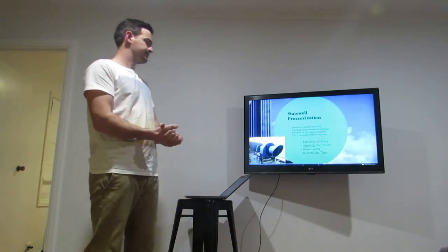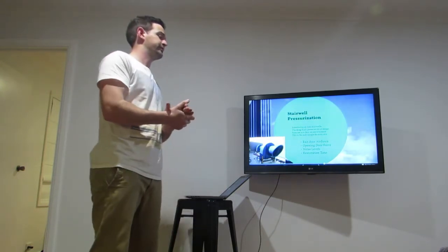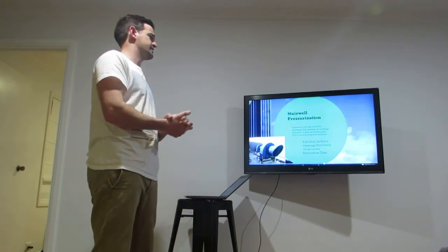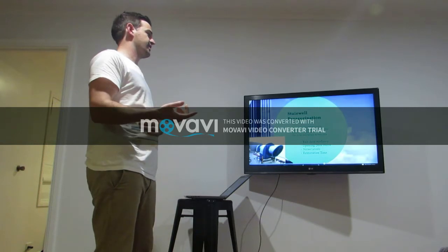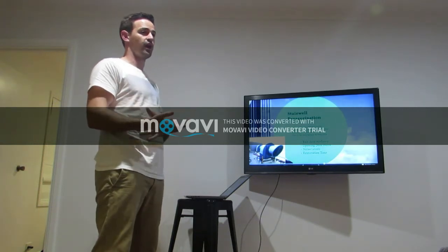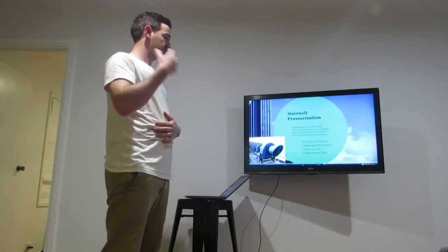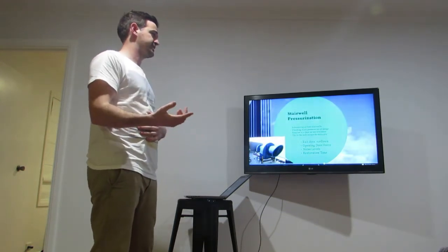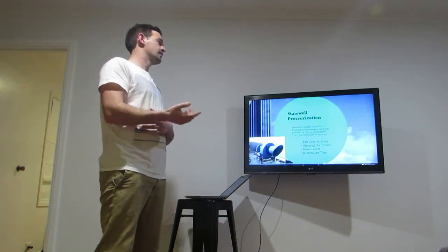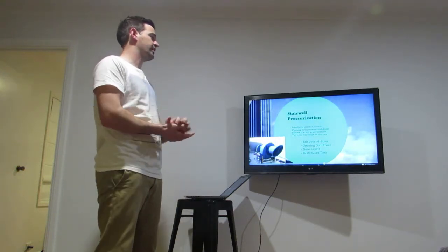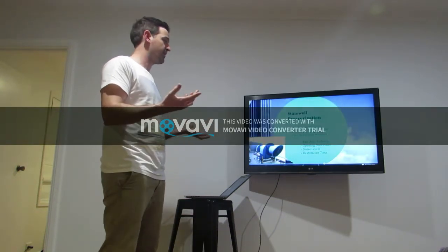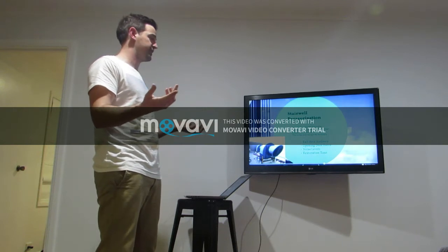Stairwell pressurisation. This is one of the most important features of essential services in HVAC. Stairwell pressurisation introduces air into the stairwell. We need to make sure the stairwells are clean and everybody has the ability to breathe and see. We check static pressures are at the design criteria. We check fans are clear in the environment, where they're bringing in the air can't be anywhere near extraction fans. They need to be free from obstruction.